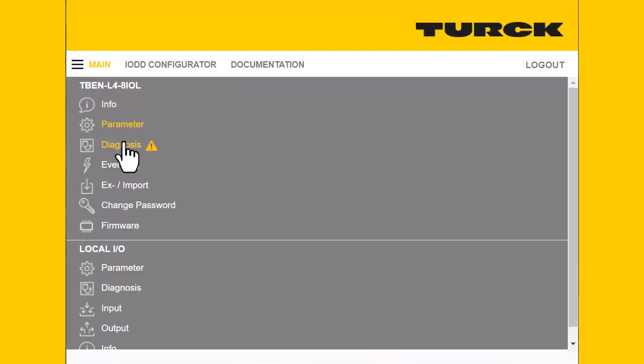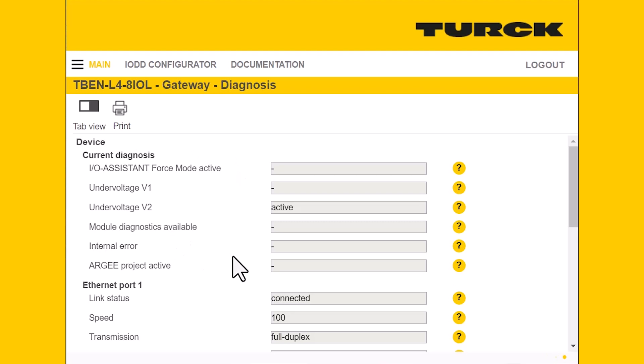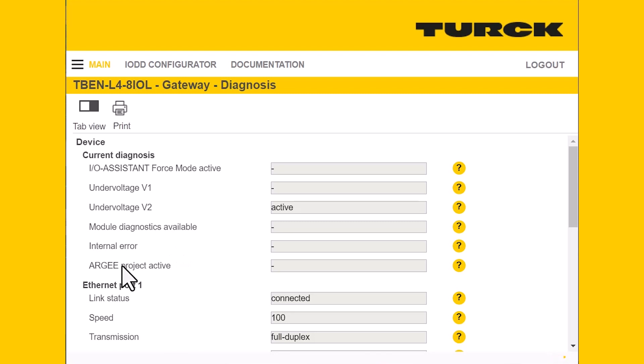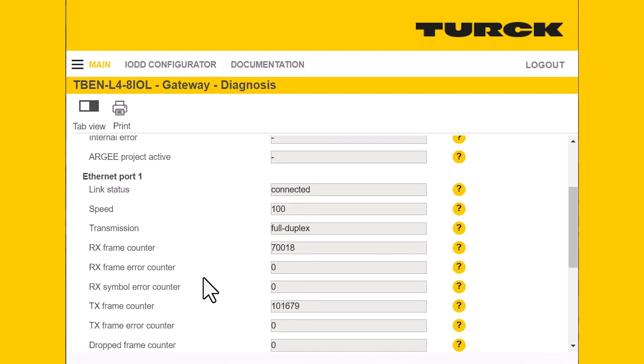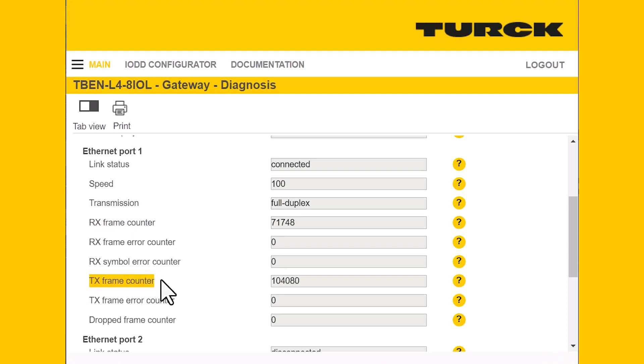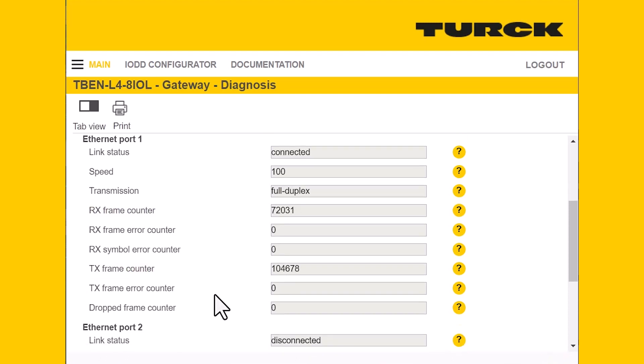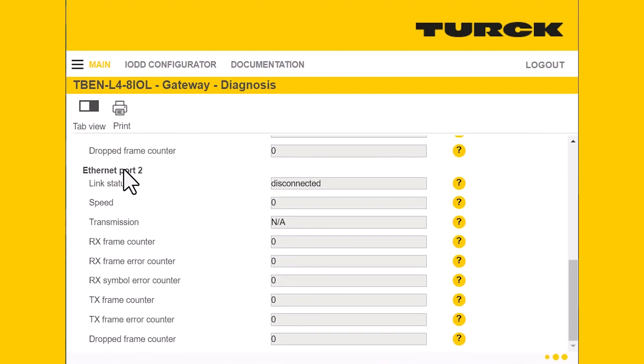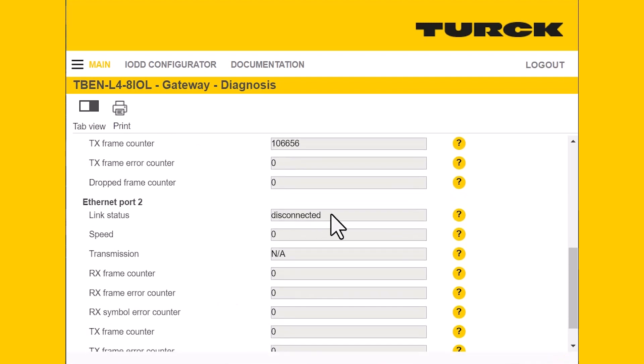Next, we'll go to the diagnostics tab. This will let us know if there are any errors with the device, such as undervoltage for either voltage group V1 or V2, whether you have an internal error, or if you have an ARGEE project running. This is also where we get information about Ethernet communication — we can see our RX and TX frame counters, which is very useful for troubleshooting network issues. We can also see Ethernet port 2; since nothing is hooked up there, it shows all zeros and indicates it's disconnected.